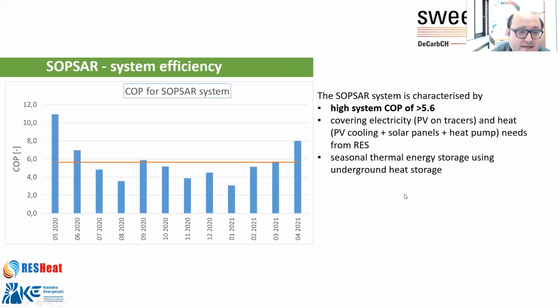So what are the results of our investigations? The heat pump COP of the system, yearly average, we were able to achieve over 5.6. This was also because the building uses floor heating, which allows a 35 degree temperature on the load side for the heat pump, which is very favorable for COP.